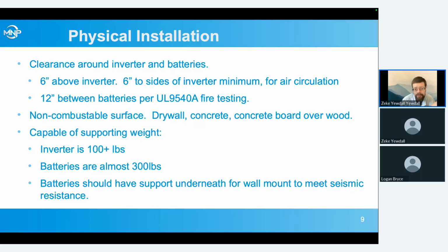For batteries, we want 12 inches between the batteries, and that's per the UL 9540A fire testing, so that if something happens to one of the batteries, it can't spread to any other batteries. So some of the cabinets and stuff which we're working on will give us a little reduced spacing there, because it's not just free air between those. We're going to have separators and things. But if you're just mounting them on the wall, you're going to have to do that 12 inches.